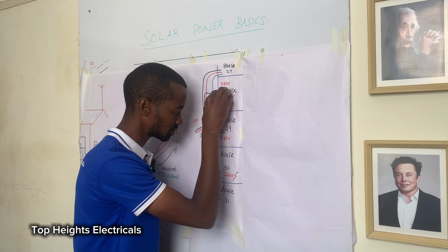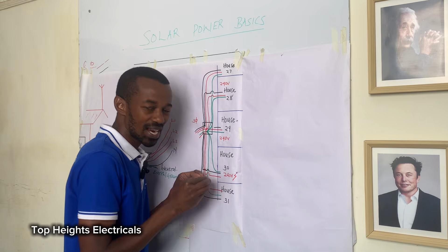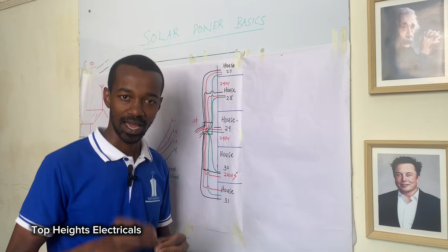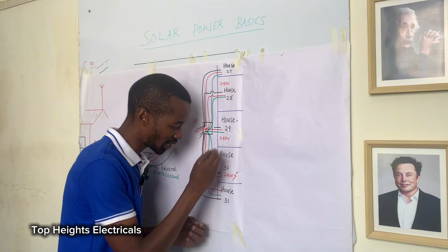Remember, each house you see here has a meter box. In my opinion, each house could have its own earth pit, inspection pit for earthing, and earth rod or earth mat, or whatever method, but each house should have an independent earth connection.